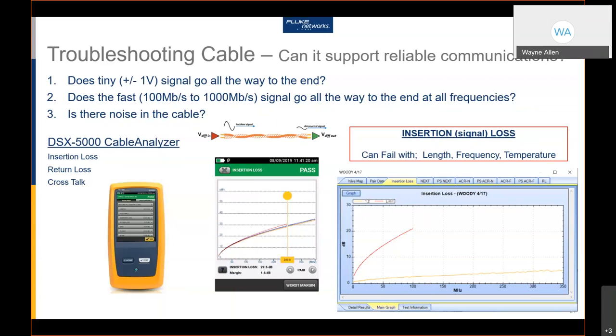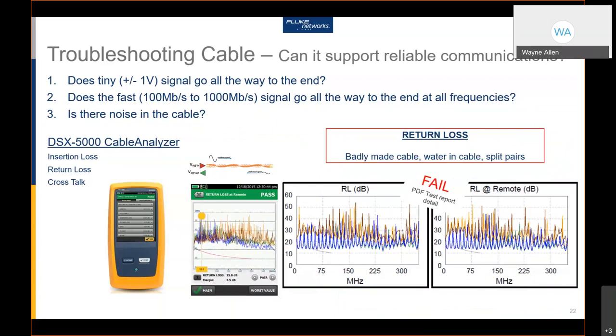If we have a return loss issue, that could be caused by water in the cable. In a wash-down environment manufacturing food or pharmaceuticals, if you use a cable designed for an office environment, even though it has a plastic jacket it is not waterproof — only water-repellent. Standard office-style cable is not IP67 rated. When water gets in, it changes the dielectric constant of the cable and you get return loss failures — so this is a way of diagnosing water-damaged cables.